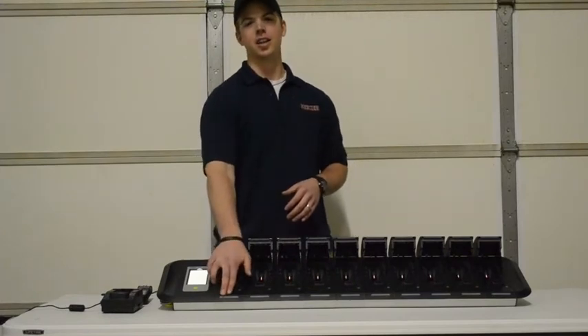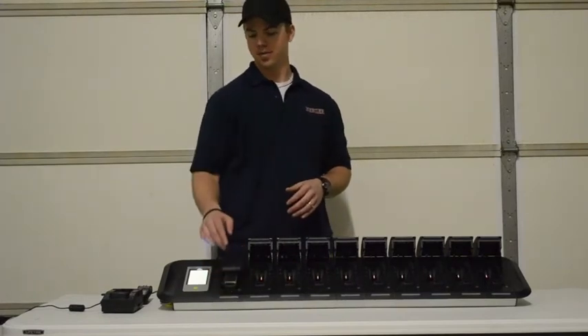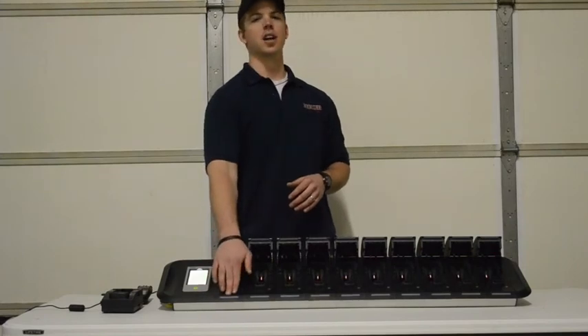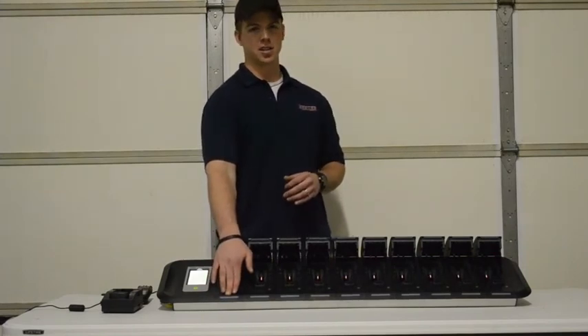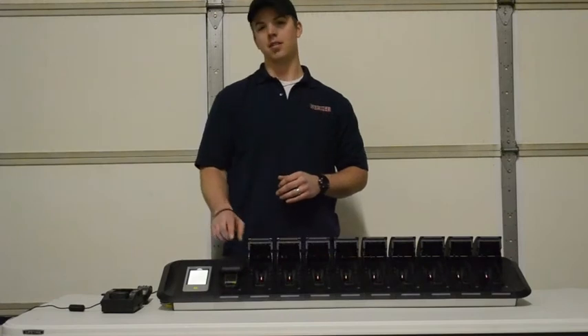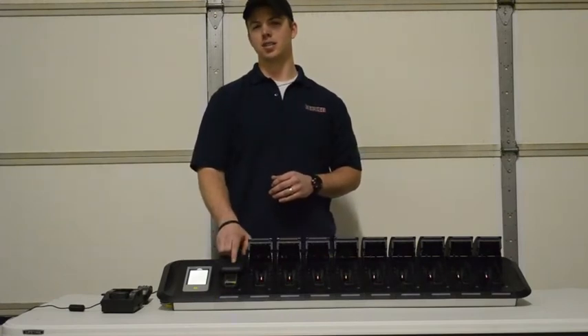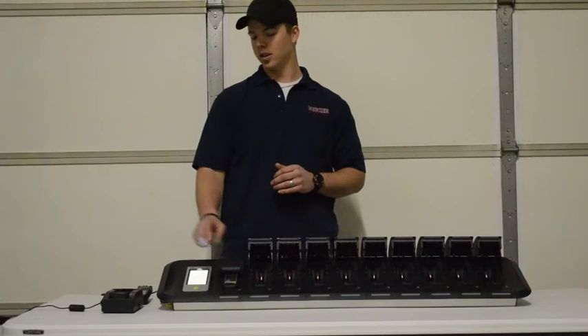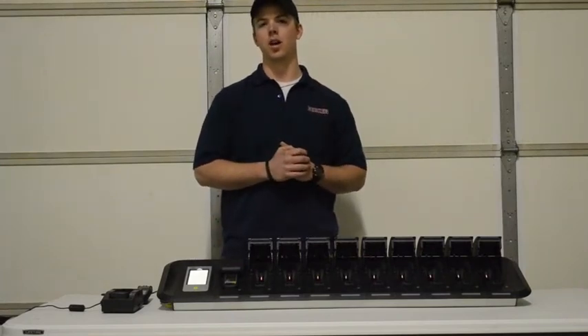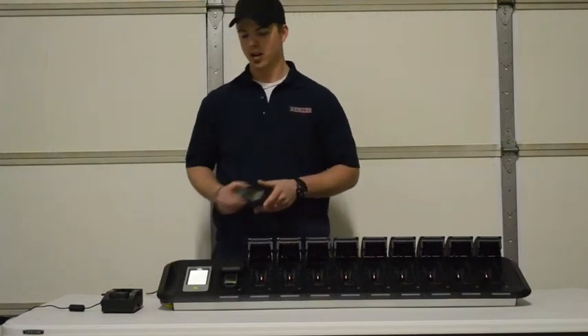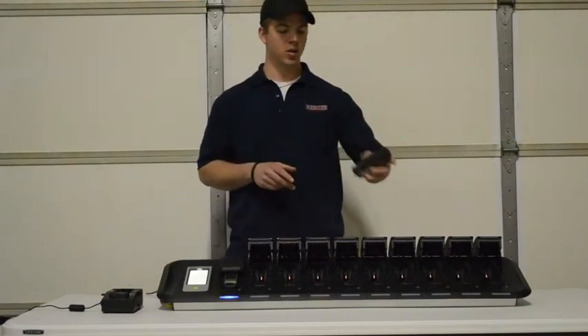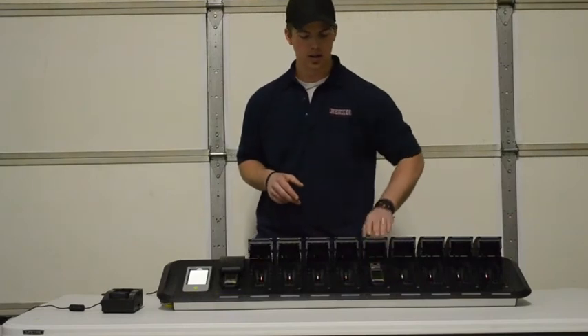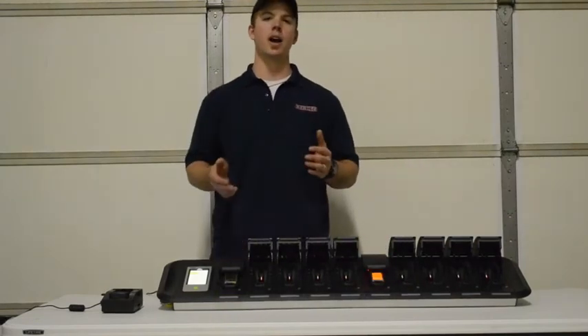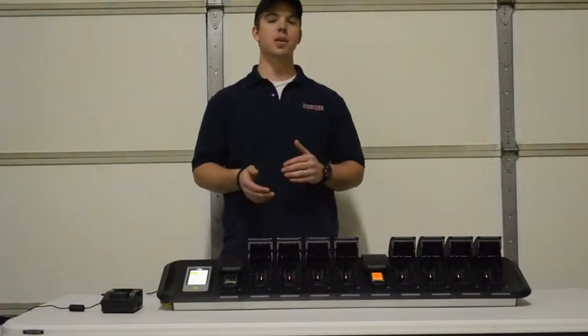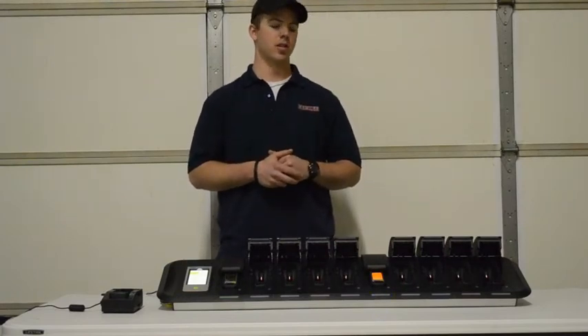The blue flashing light indicates that there's a test in progress. If the LED is flashing green, it means the test has passed successfully. If the LED is flashing red, it means the test has failed. If the test has failed, you can click the touch screen and it'll give you more information of what's going on with your monitor. Your monitor doesn't even need to be on to do a bump test. Simply drop it in and it'll automatically turn on your monitor. It takes a little bit longer, but you don't even have to turn it on.